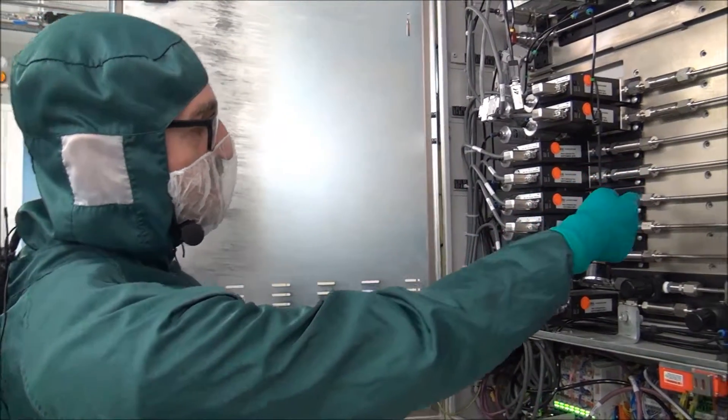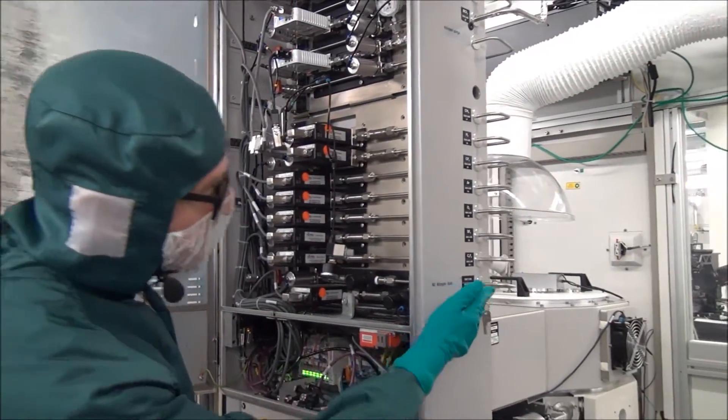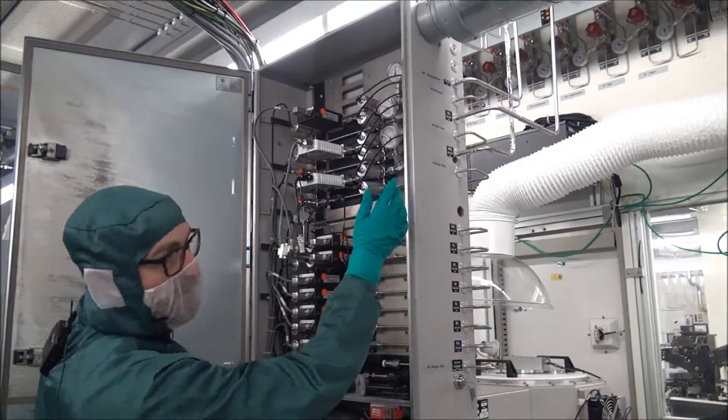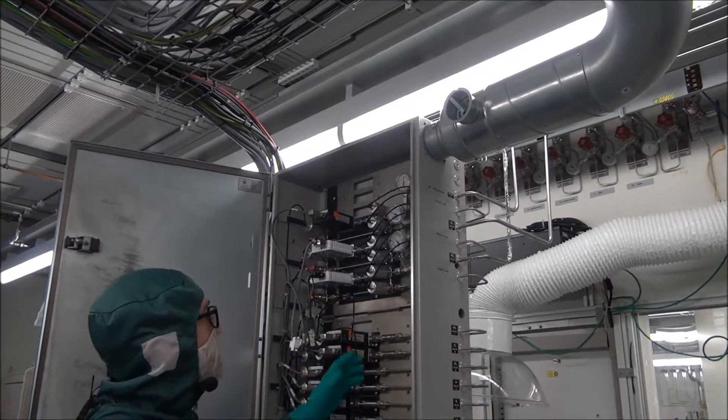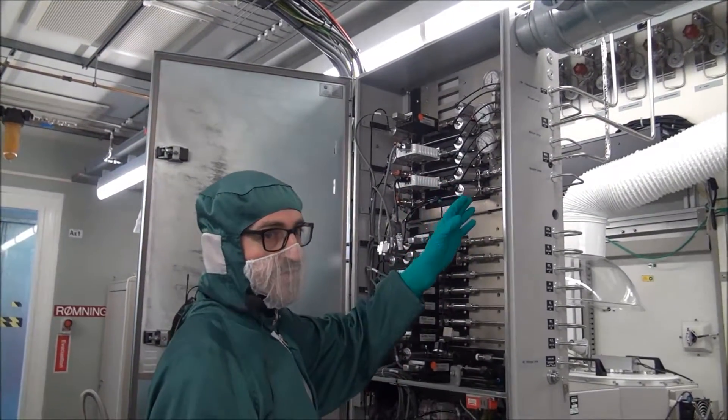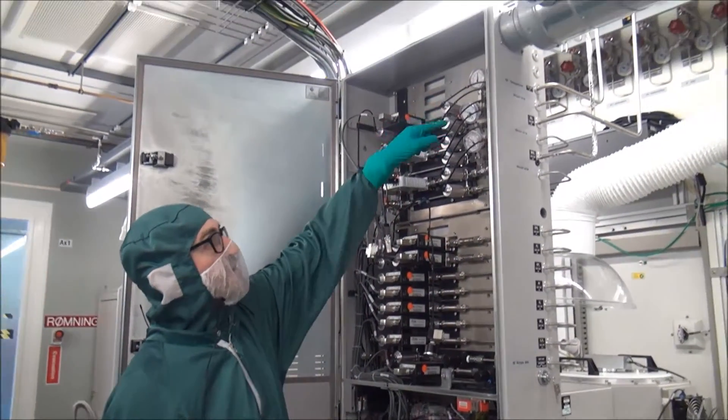And then we have some filters just before the mass flow controllers. And if you look on the right hand side you can also see where all the gases are coming in, up at the top part of the gas box. So we have the toxic gases, and on this particular system we have BCL3, CL2, and HBr. And you can also see them on the pressure gauges too.